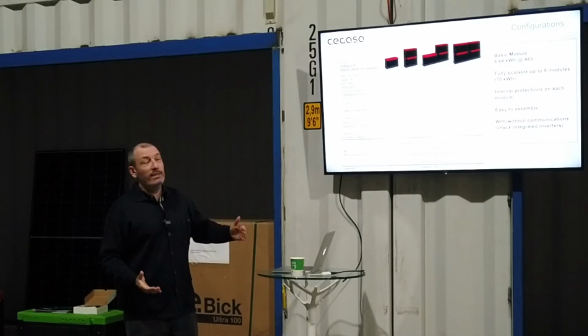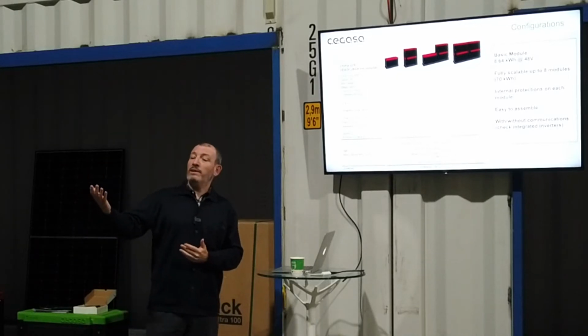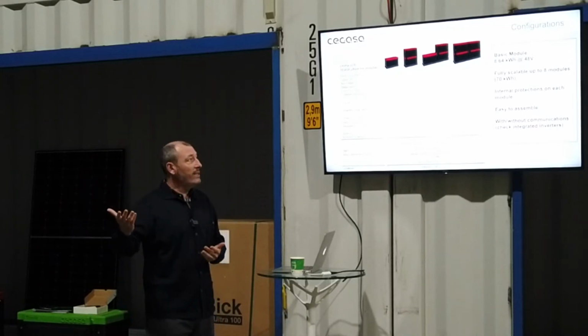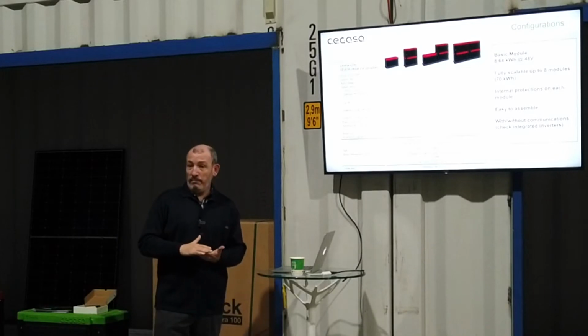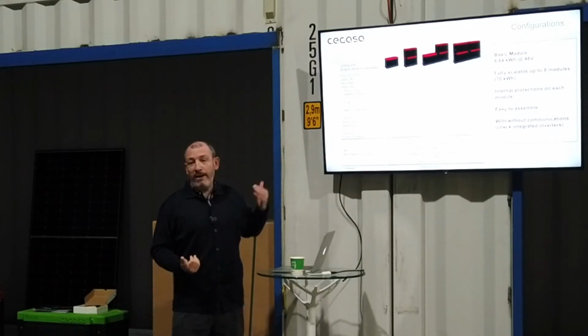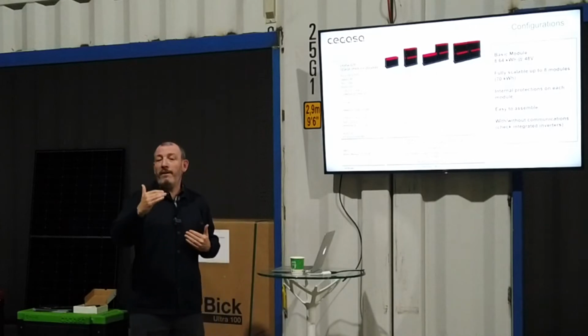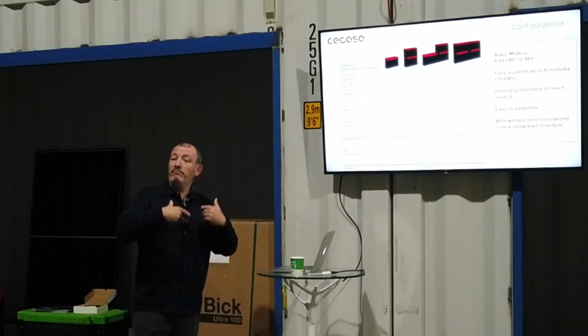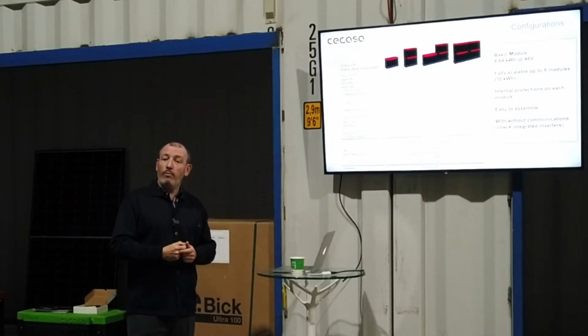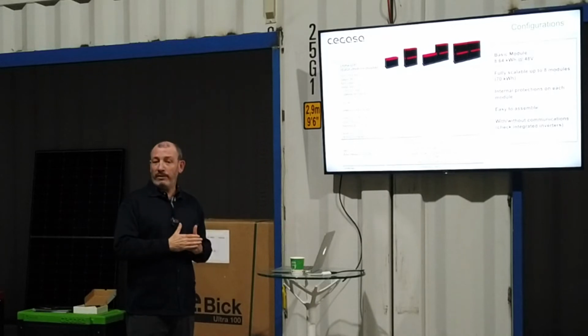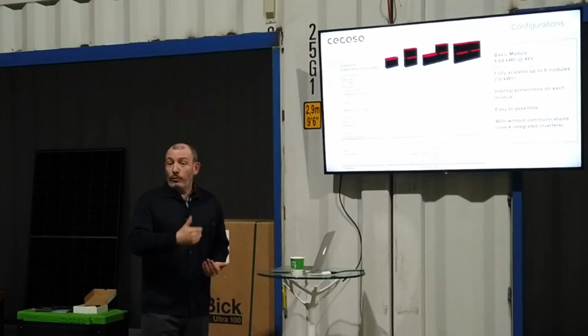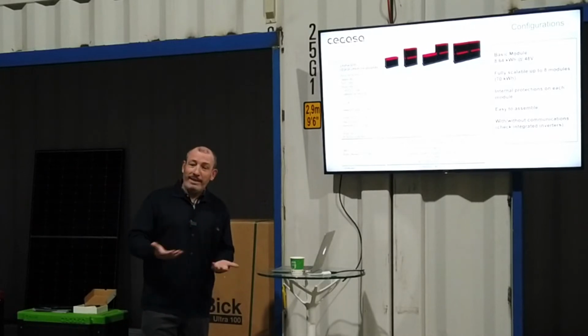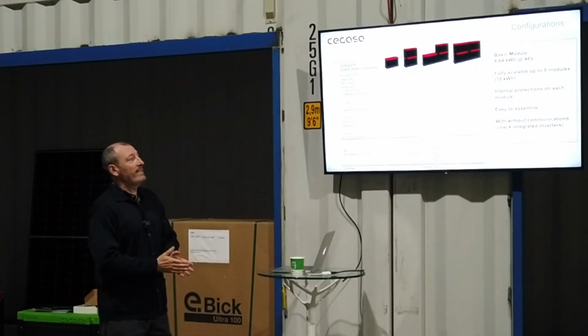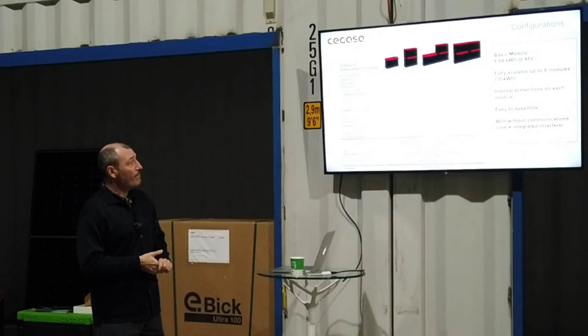Another issue is, considering that lithium doesn't go over 60 degrees, where do you set the limit? In our case, it's 55. At 55, the protections will open the contactor in order to protect the battery. But again, even if we wanted, we couldn't go to 65 because lithium doesn't accept 65. So that's the point.